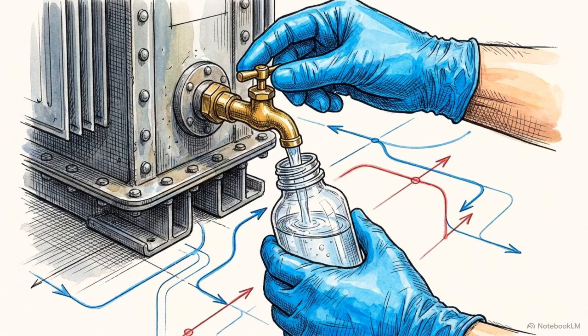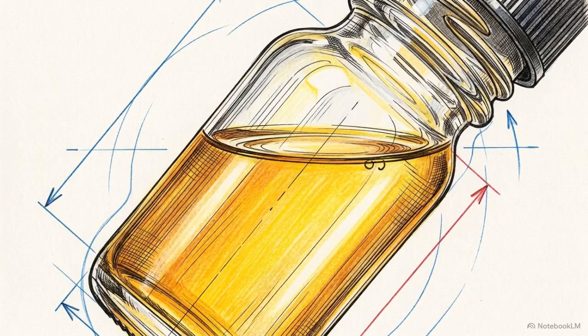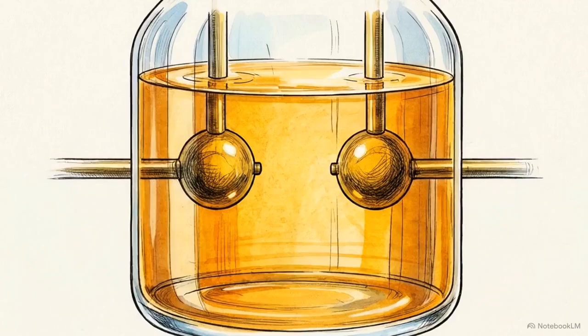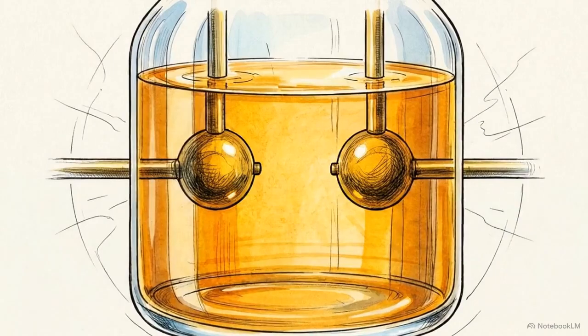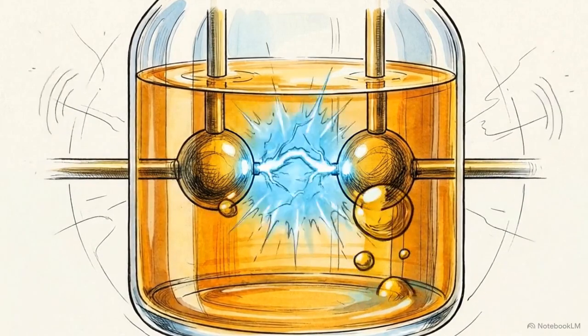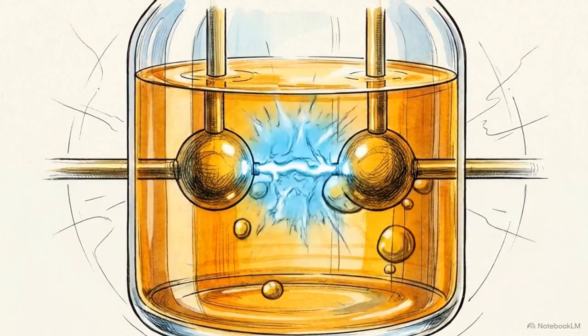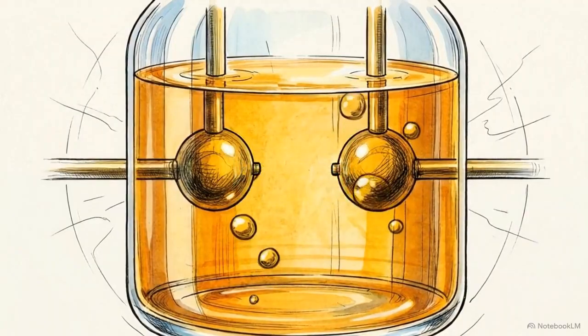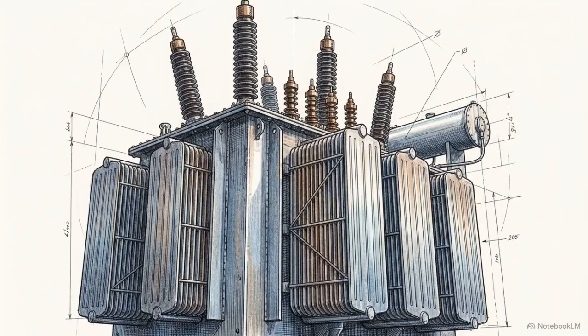We then extract fluid for the oil dielectric breakdown test. The sample handling is precise. Technicians must avoid introducing air bubbles, ambient moisture, or particulate matter that would skew the dielectric strength readings. Inside the test cup, voltage ramps up across submerged electrodes until the oil literally arcs over. We run multiple breakdowns to calculate the final average. Together, these tests prove the dielectric container is physically sound and ready to manage high-voltage stress without internal tracking, arcing, or failure.